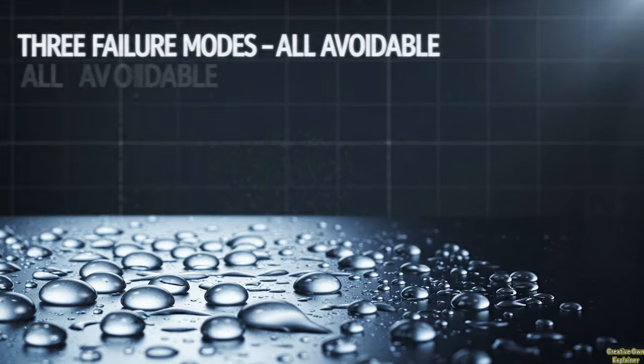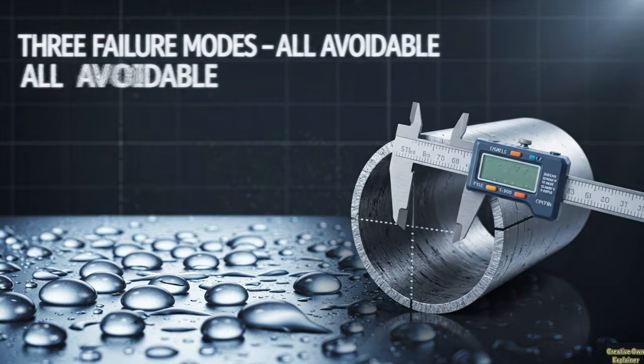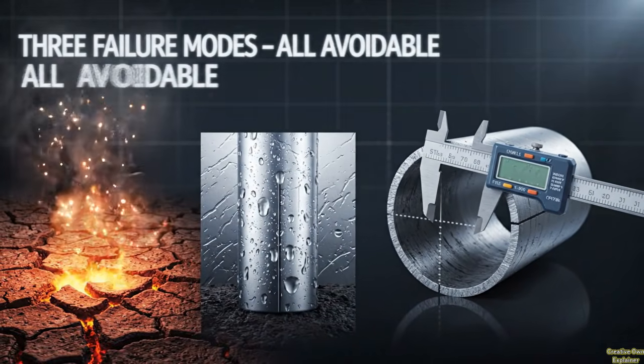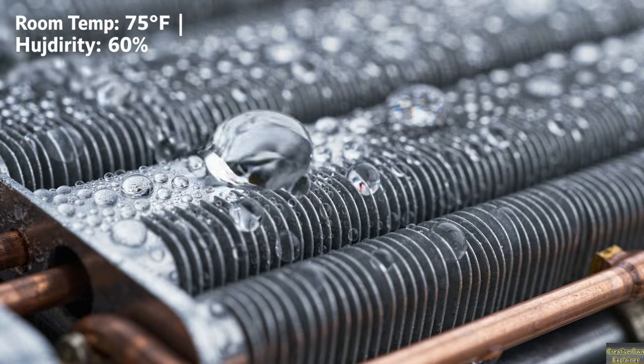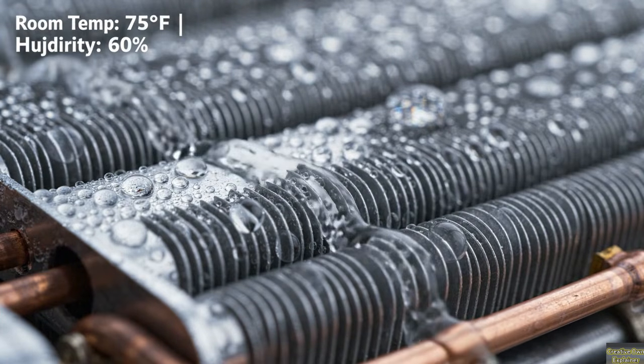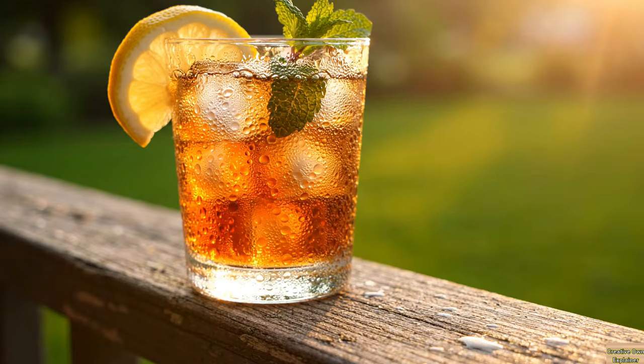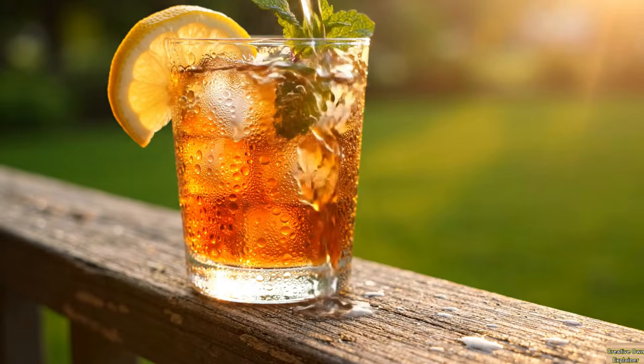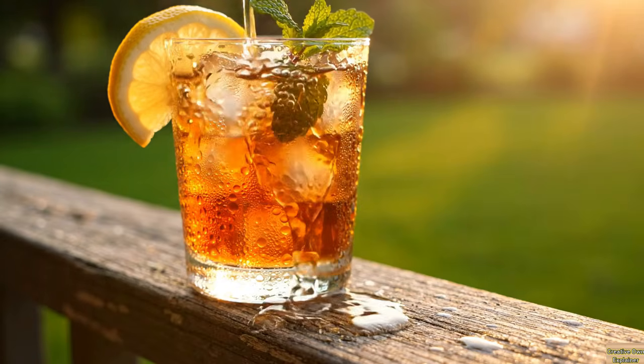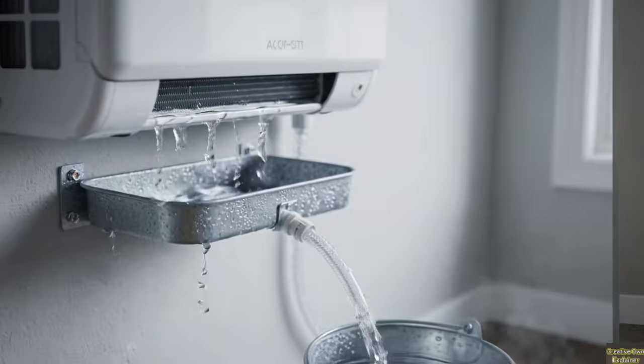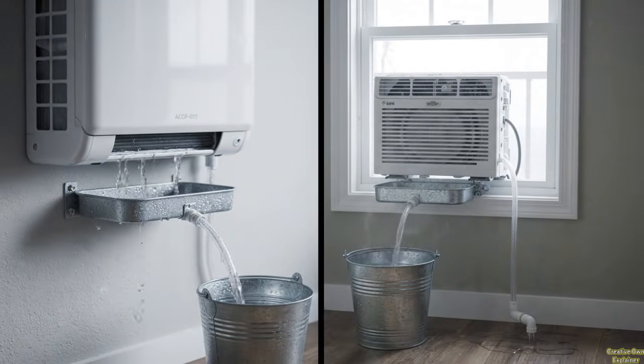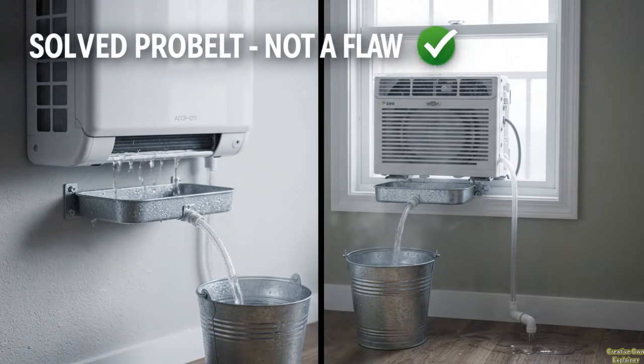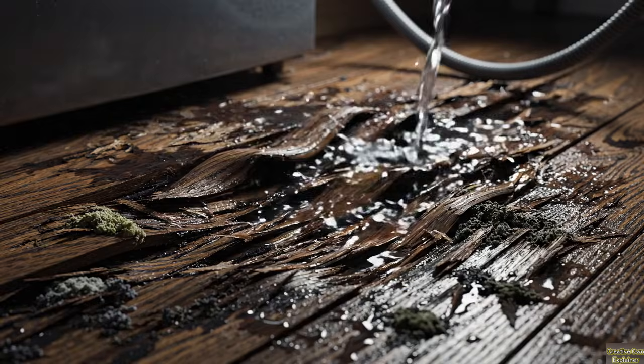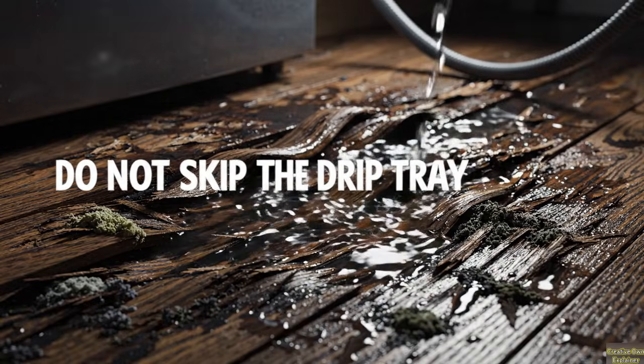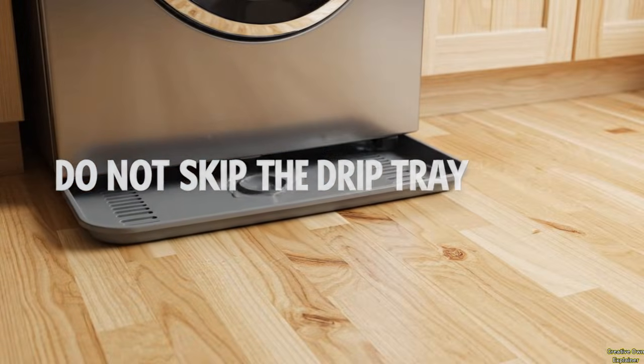Let me address the 3 failure modes now, because the failures are real. They are just all avoidable. The first problem is condensation. When you push 55-degree water through a radiator in a room with 75-degree air and 60% humidity, you get condensation on the cold surface, the same way a glass of iced tea sweats on a summer porch. The fix is a drip tray beneath the heater core and a gravity drain routed to a bucket or a floor drain. Every window air conditioner in America deals with this same problem the same way. It is a solved issue, not a design flaw. Do not skip the drip tray.